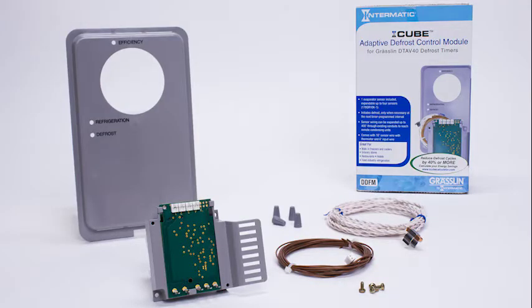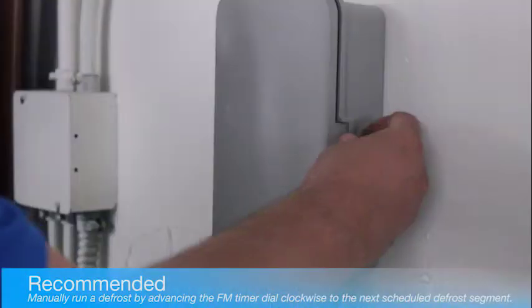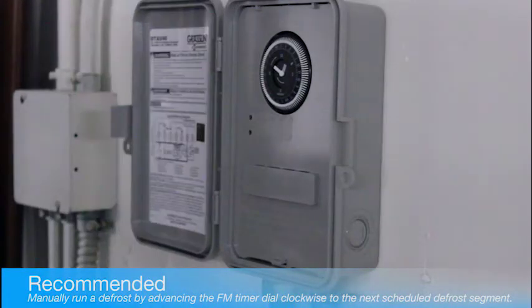This is a retrofit demonstration to a field-installed Grasslin DTAV40 timer controlling electric defrost in a walk-in freezer. The Icube Adaptive Defrost Module comes with 10 feet of thermistor wire, 6 feet of input lead wire, a protective insulator panel, screws, and wire nuts. Before the install, we recommend initiating a manual defrost so coils are frost-free. You can manually run a defrost by advancing the FM timer dial clockwise to the next scheduled defrost segment.